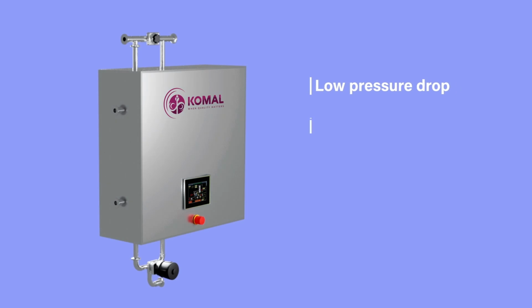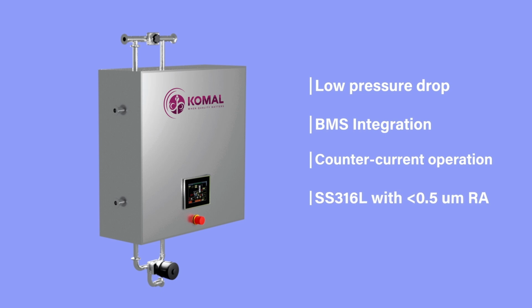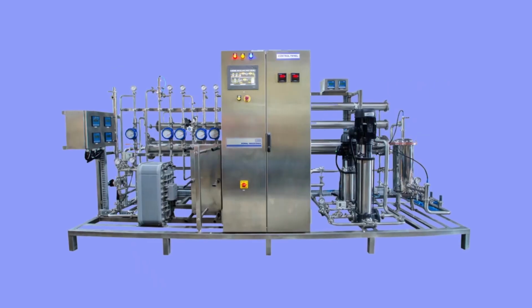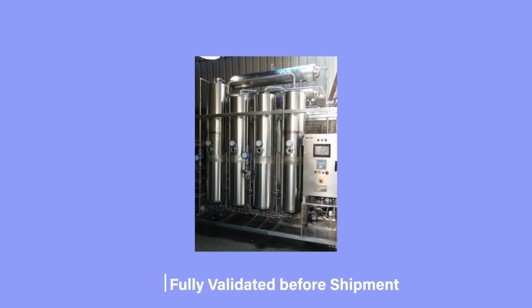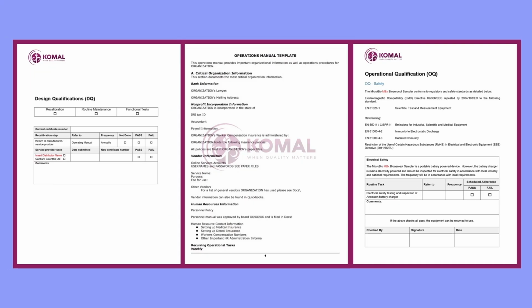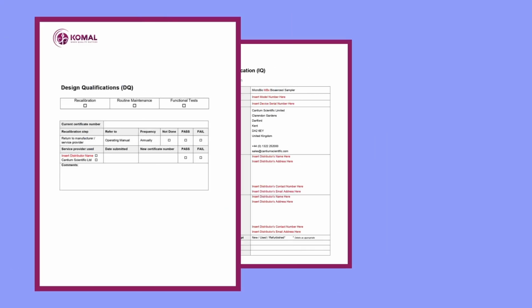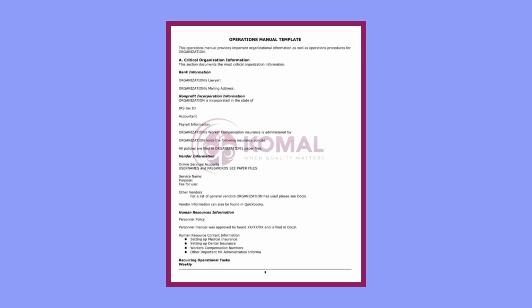The HMI shows all the important parameters and can be accessed remotely or can be integrated into any building management system. The heat exchanger operates in a countercurrent manner which increases the heat transfer. All contact parts are SS316L, with less than 0.5 micrometer Ra value and ASME BPE compliant. The entire storage and distribution system is fully tested and validated before shipment, and all the necessary documents like the DQ, IQ, OQ and manuals are provided with the system.